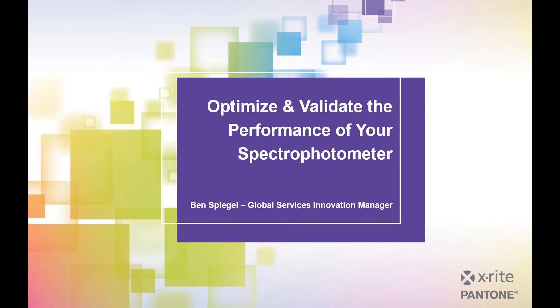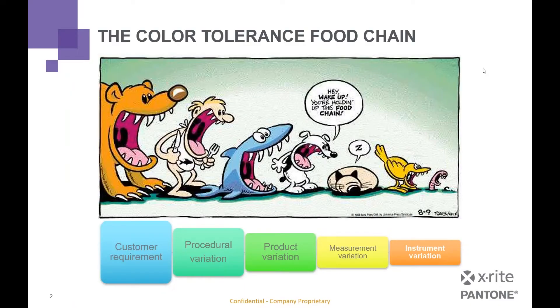Thank you, Robert. Hello everyone. Thank you for joining us today to talk about ways to optimize and validate the performance of your spectrophotometers. To start out, we want to look at the color tolerance food chain. We're all working towards our customer requirements — that end tolerance the process needs to return. As you go deeper into the process, tolerances get tighter and tighter due to stack-up throughout production. At the very bottom of the food chain is instrument variation, which needs to be the tightest of all, since it could potentially introduce the most variation and reduce the tolerance band for the rest of production. That's what we're going to be focusing on today.